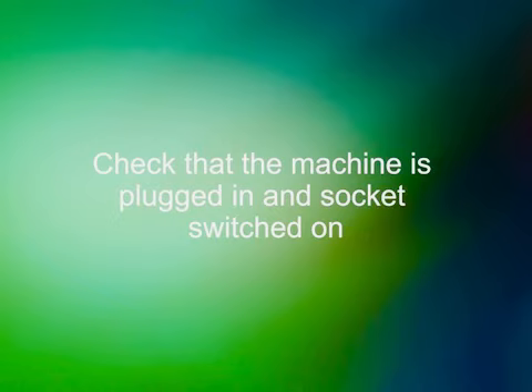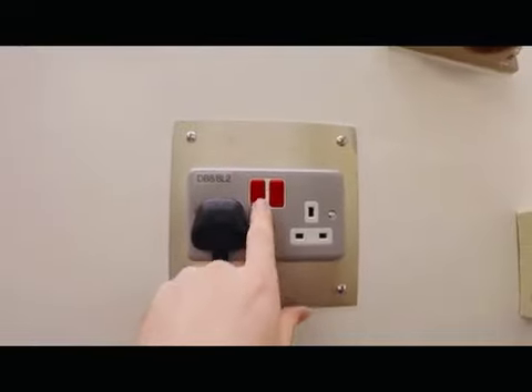On the Blease anaesthetic machine used as part of IAC testing. Firstly, check that the power supply for the anaesthetic machine, monitor and ventilator, if applicable, is plugged in and switched on. Ensure that the anaesthetic machine is switched on at the front.